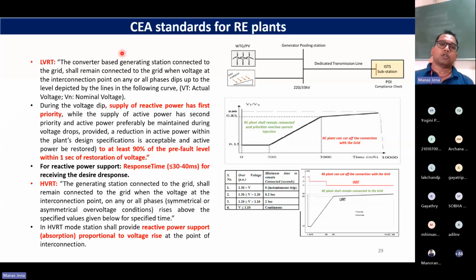So once we saw a couple of problems, I mentioned that different standards are now coming up, okay, whether it is the North American standard, the German grid codes, or in India the grid codes from the CEA. What is it asking the inverter owners or the plants to do? Two very important things they are supposed to do. The first is low voltage ride through, okay. What does it mean? I'll go back to my previous example. If you are a good friend, you will stand with your friend during his or her bad times. That is the meaning of LVRT, low voltage ride through, okay.